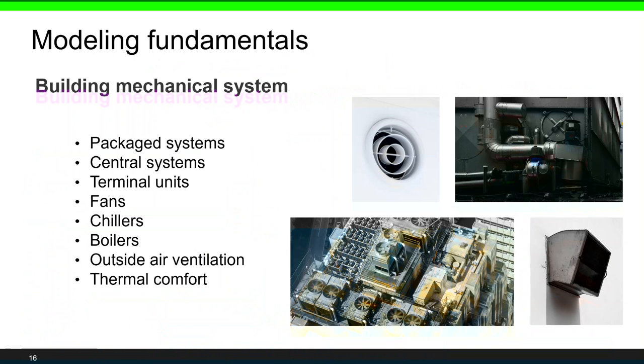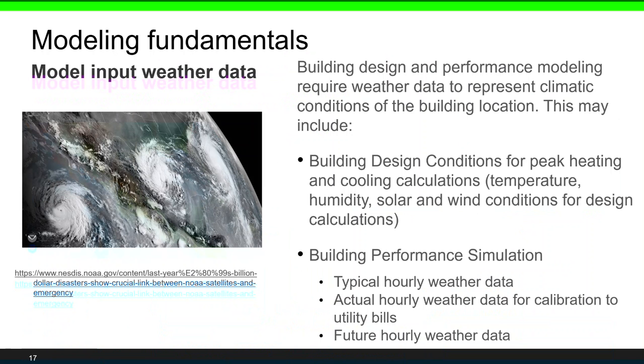For the mechanical system, building models can cover a variety of actual building systems, including central systems, chillers, terminal units, boilers, etc. Another important input is weather data, which is critical for building energy modeling. Building design conditions for peak heating and cooling calculations depend on weather, and building performance simulation also depends on weather. There are different types of weather data available: typical hourly weather data, actual hourly weather data, and future hourly weather data — and the choice depends on the purpose of the building energy modeling.